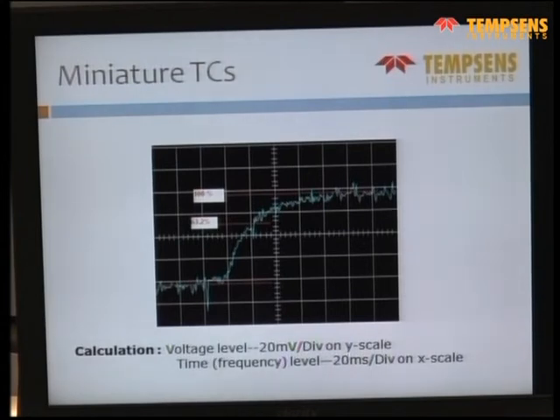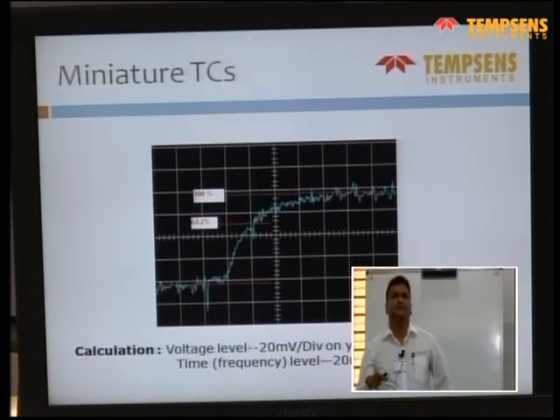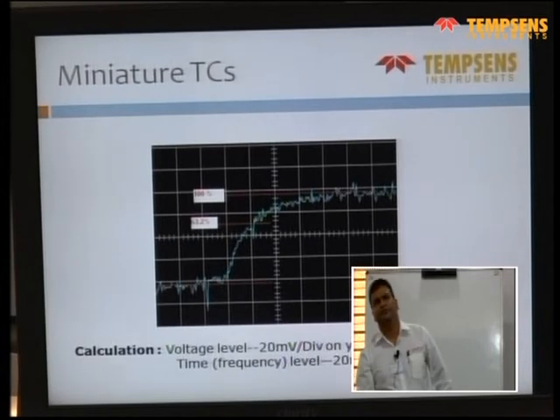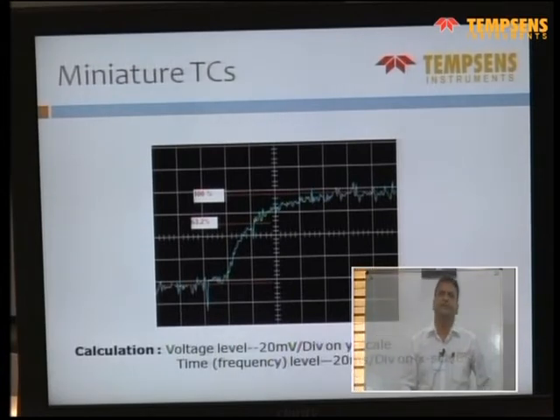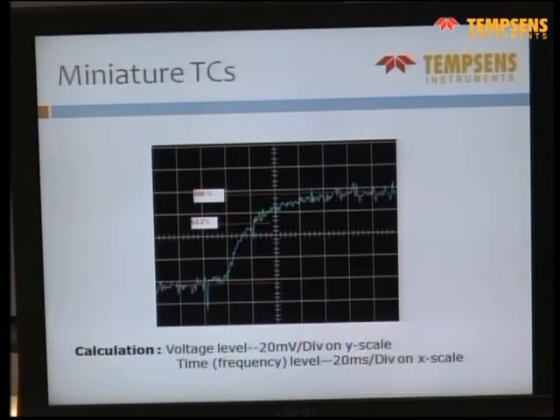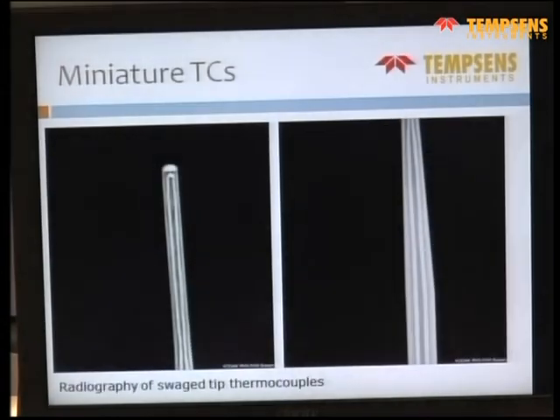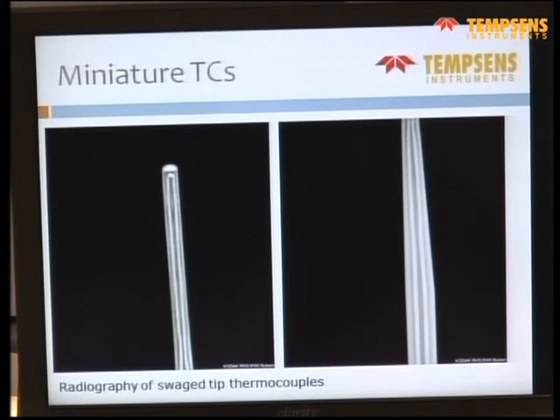Here you can see the response time check we did for the customer. So T63 was about 30 milliseconds. Each T63 was close to about 30 milliseconds. Each division is about 20 milliseconds, and this is a swage thermocouple. You can see it is narrowed from the bottom so that the tip is thinner and the rest of the thermocouple is bigger.